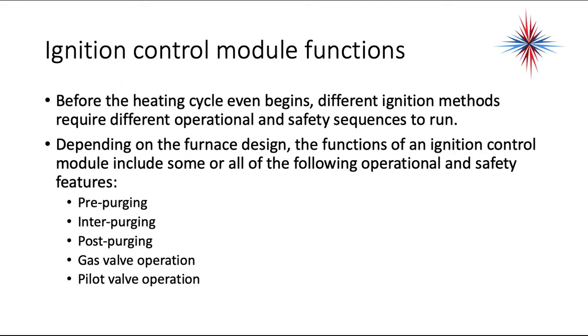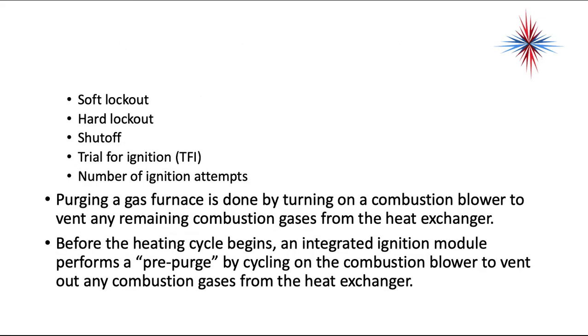So let's go over the ignition control module functions. Before the heating cycle even begins, different ignition modules require different operational and safety sequences to run. Depending on the furnace design, the function of an ignition module includes some or all of the following operational and safety features: pre-purge, inter-purging, post-purging, gas valve operation, pilot valve operation, soft lockout, hard lockout, shut off, trial for ignition, number of ignition attempts.